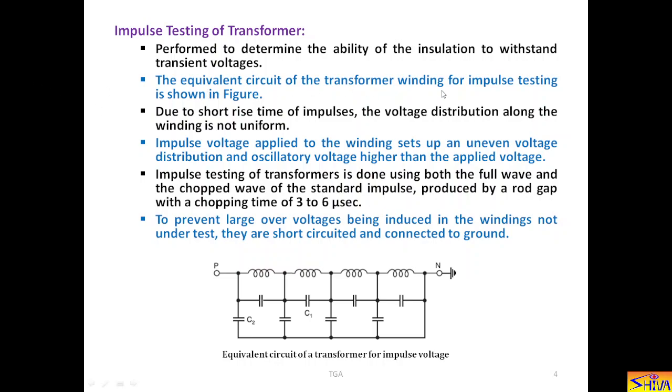The equivalent circuit of the transformer winding for impulse testing is shown in the figure. This is the electrical equivalent circuit. Due to short rise time of the impulses, the voltage distribution along the winding is not uniform. This is because the d by dt is very high. Therefore, the voltage distribution in the winding is not uniform.